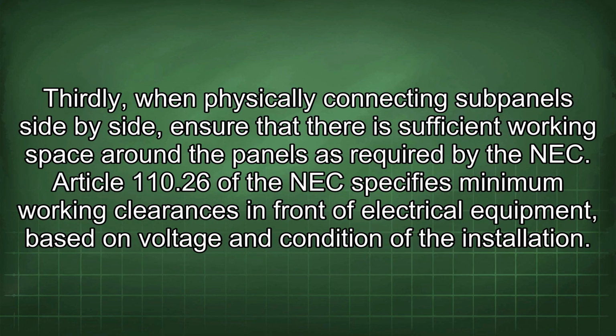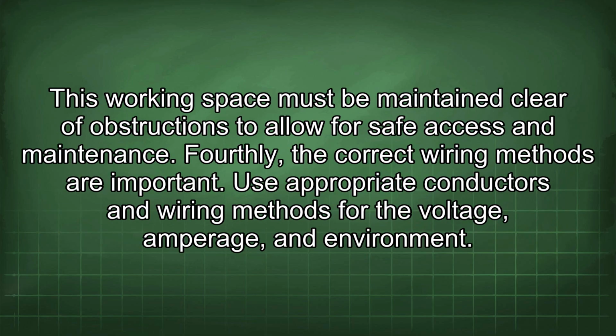Thirdly, when physically connecting subpanels side by side, ensure that there is sufficient working space around the panels as required by the NEC. Article 110.26 of the NEC specifies minimum working clearances in front of electrical equipment based on voltage and condition of the installation. This working space must be maintained clear of obstructions to allow for safe access and maintenance.